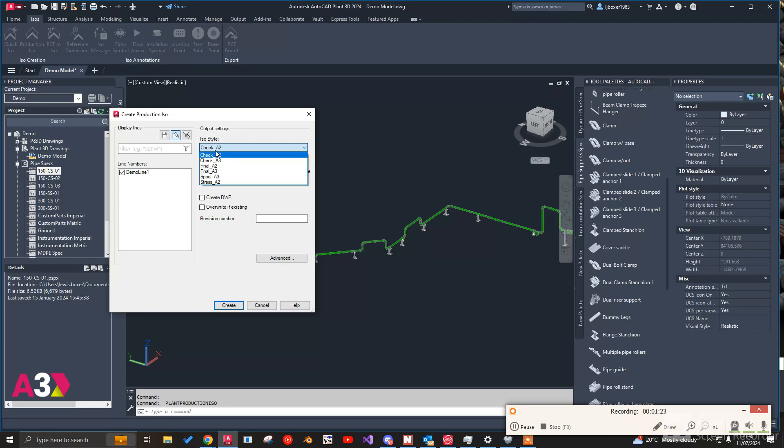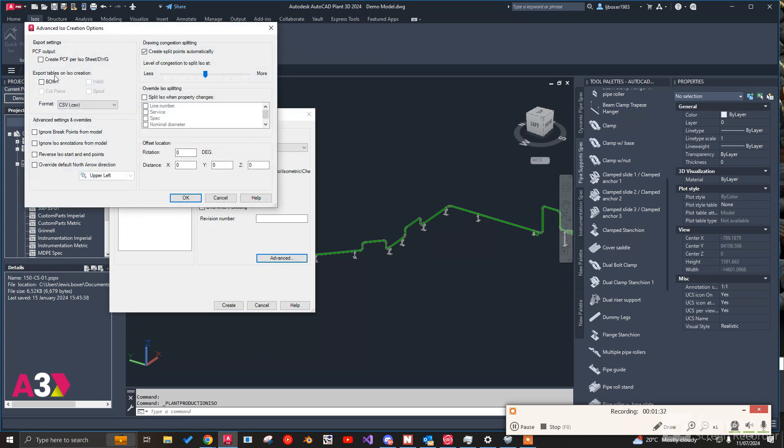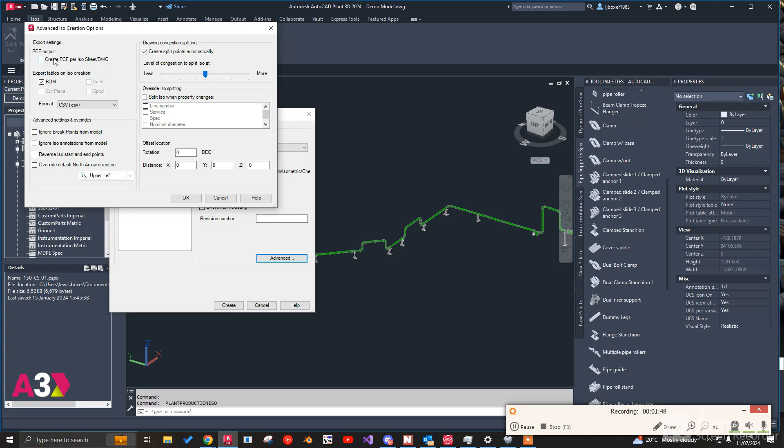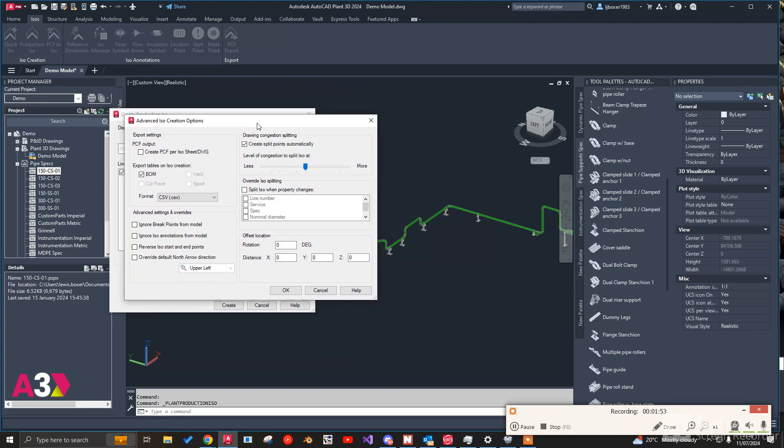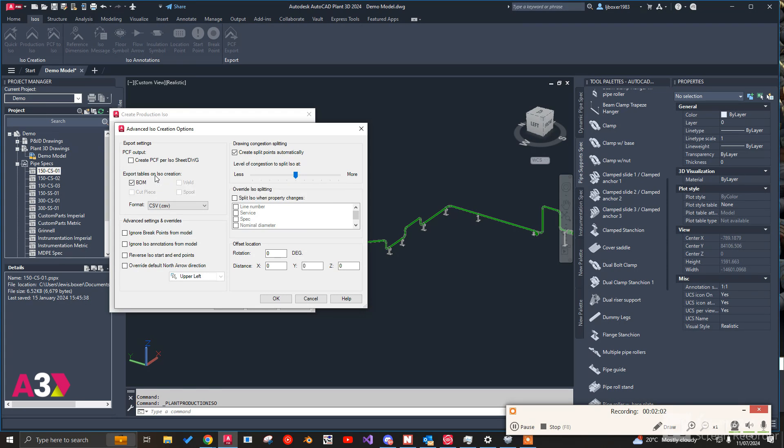And what we can do is now come over to the isometrics, produce a production iso. There's our line. We've got the ability to produce different isometric styles and we customize these to our customers' borders and whatnot. And we've got the ability to export the table, the bill of materials table into a comma separated value file, basically an Excel file. The ability to create offsets and whatnot. And even the ability to export the isometric as a PCF file. So for those who don't know, a PCF file format is a text file format which most commonly can be used for Caesar analysis.